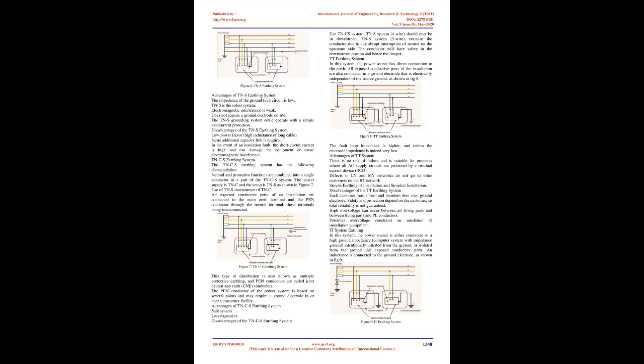TN-C-S earthing system. The TN-C-S earthing system has the following characteristics. Neutral and protective functions are combined into a single conductor in a part of the TN-C-S system. The power supply is TN-C and the setup is TN-S as shown in Figure 7. Use of TN-S downstream of TN-C. All exposed conductive parts of an installation are connected to the main earth terminal and the PEN conductor through the neutral terminal, these terminals being interconnected. This type of distribution is also known as multiple protective earthing, and PEN conductors are called combined neutral and earth, CNE, conductors. The PEN conductor of the power system is earthed at several points and may require a ground electrode in or near a consumer facility.